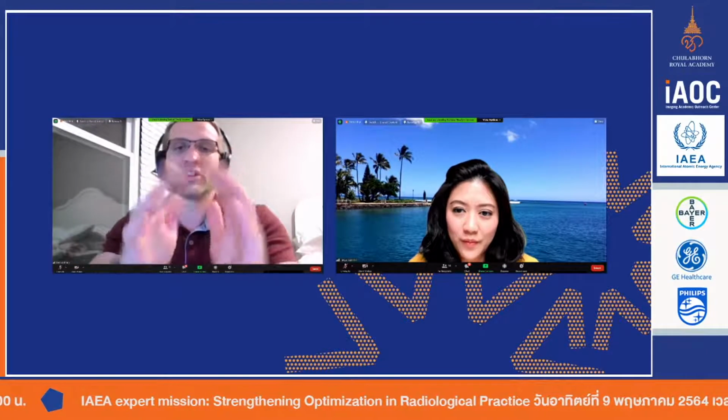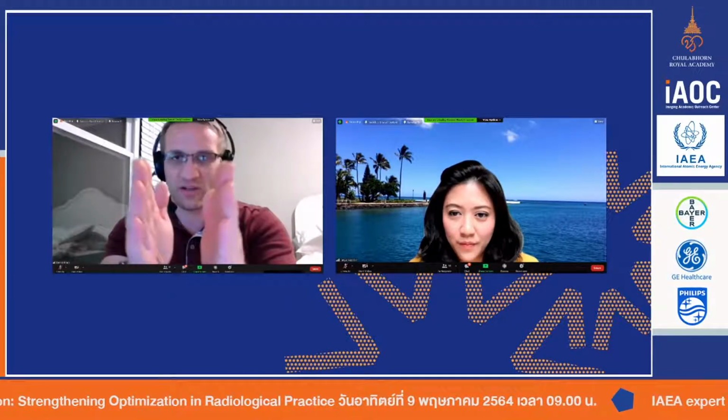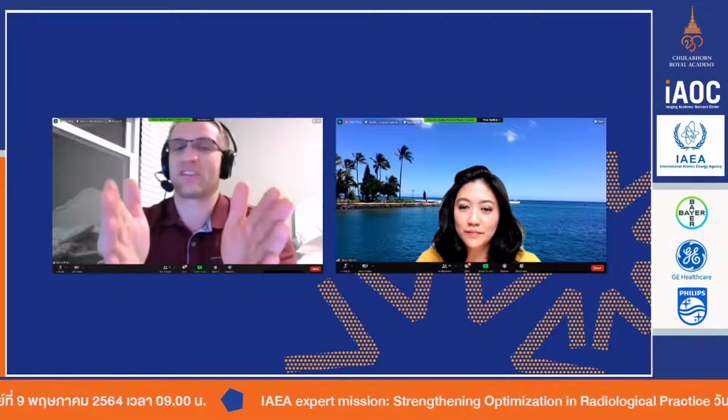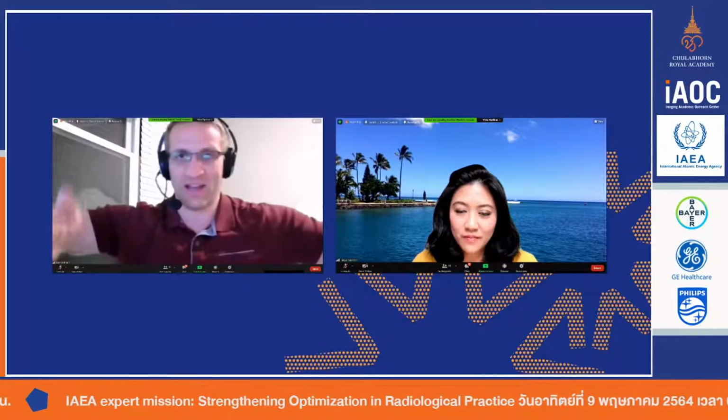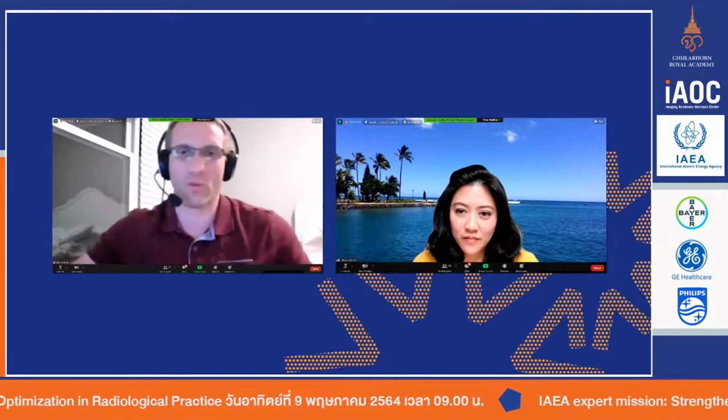Okay. But that's why what we say is, it really depends on the radiologist. It really depends on your hospital. And so look at your distribution. And then I would say, look at 1 standard deviation, look at 2 standard deviations. As a publication, just as a group of scientists, we got together and said, plus or minus 2 standard deviations is actually a pretty big jump. That's all the way out there at the 8, 9, 10 DI value. And so we should probably start to look at images and start to ask ourselves, why are we so far away from the median?